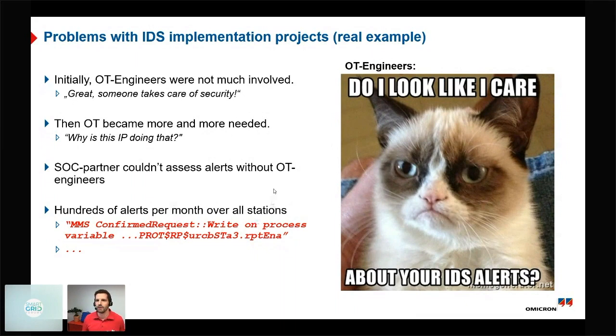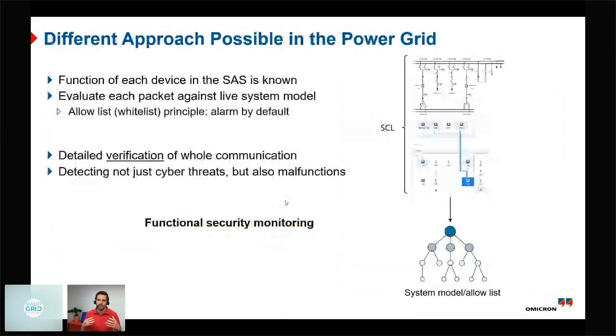In digital substations, or in any other modern substation with substation automation systems, there is a different approach possible, which does not depend on baseline based learning or an AI approach, because these devices in a substation automation system on the process bus and station bus have functions that are actually quite known beforehand. It's known how these devices behave, and it's known what they communicate and when. And with the 61850 substation, there is even an SCL file available.